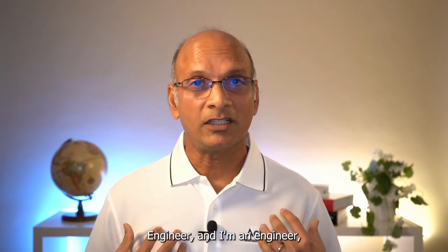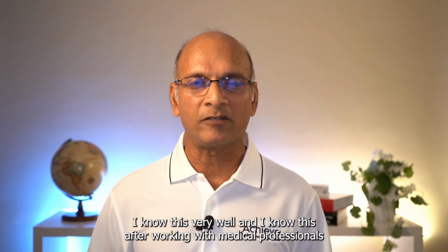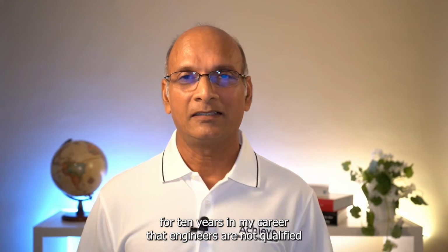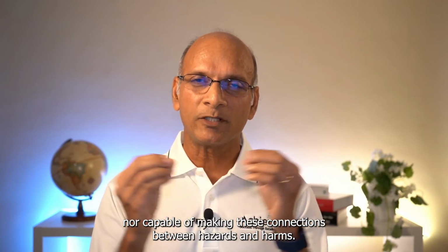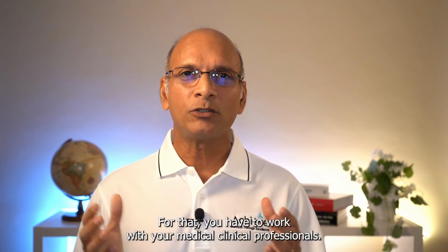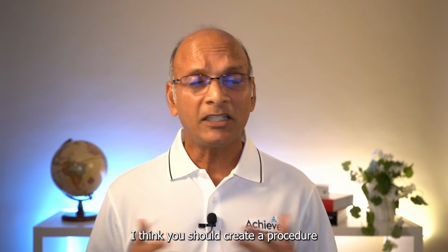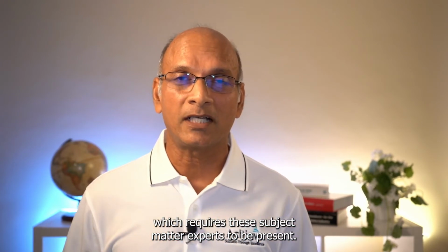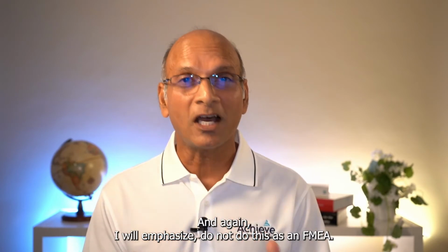Engineers, and I'm an engineer, I know this very well, and I know this after working with medical professionals for 10 years in my career, that engineers are not qualified nor capable of making these connections between hazards and harms. For that, you have to work with your medical clinical professionals. I think you should create a procedure which requires these subject matter experts to be present. And again, I will emphasize, do not do this as an FMEA.